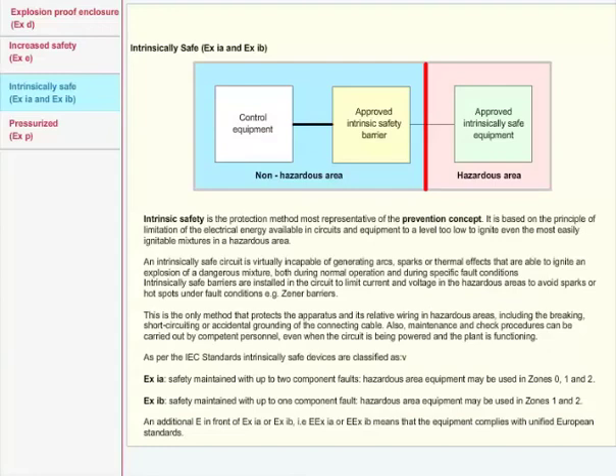Intrinsically safe, Ex ia and Ex ib. Intrinsic safety is the protection method that is most representative of the prevention concept. It is based on the principle of limitation of the electrical energy available in circuits and equipment to a level too low to ignite even the most easily ignitable mixtures in a hazardous area. An intrinsically safe circuit is virtually incapable of generating arcs, sparks, or thermal effects that are able to ignite an explosion of a dangerous mixture, both during normal operation and during specific fault conditions.